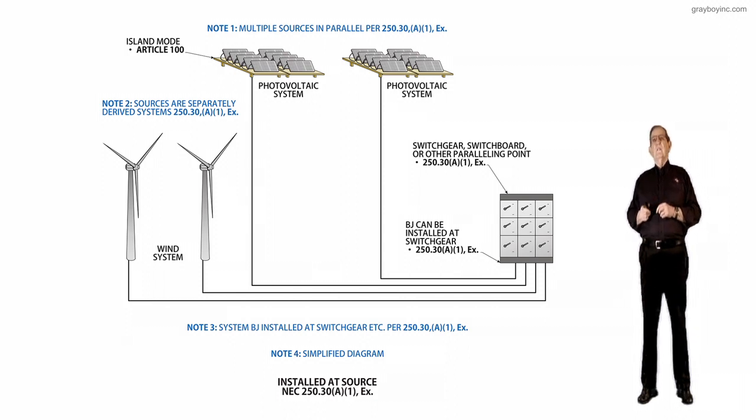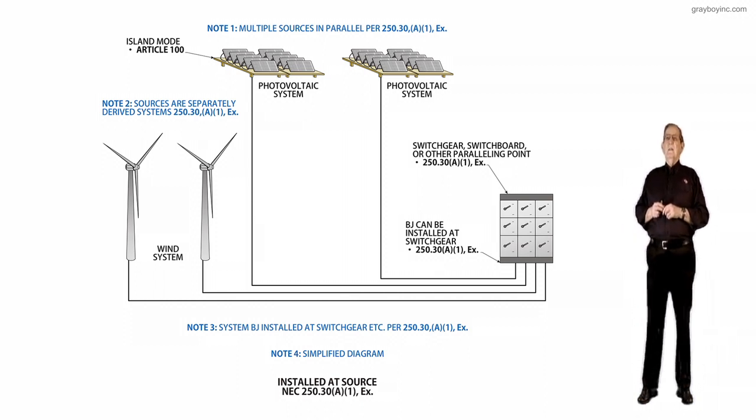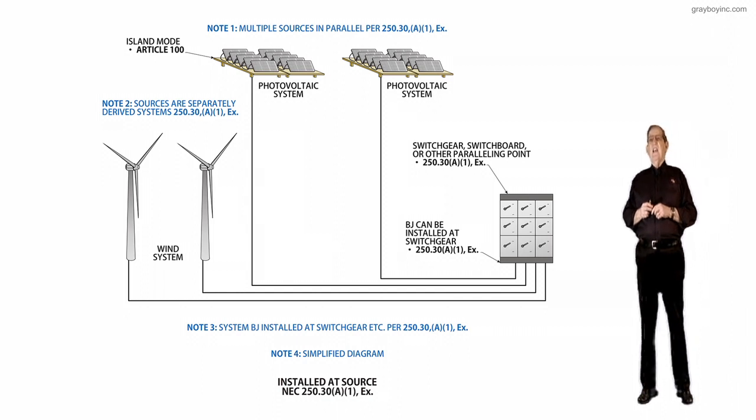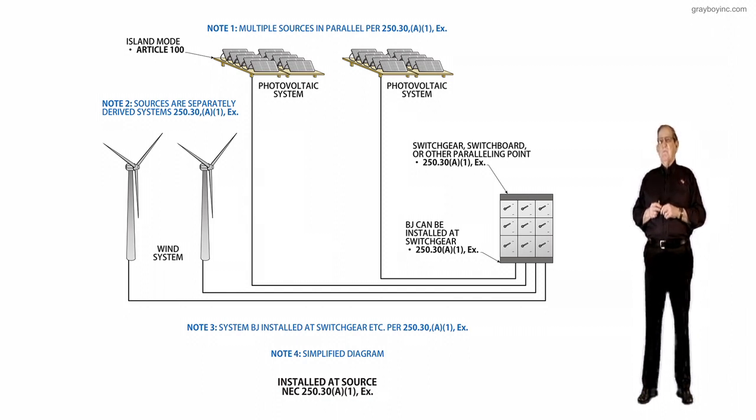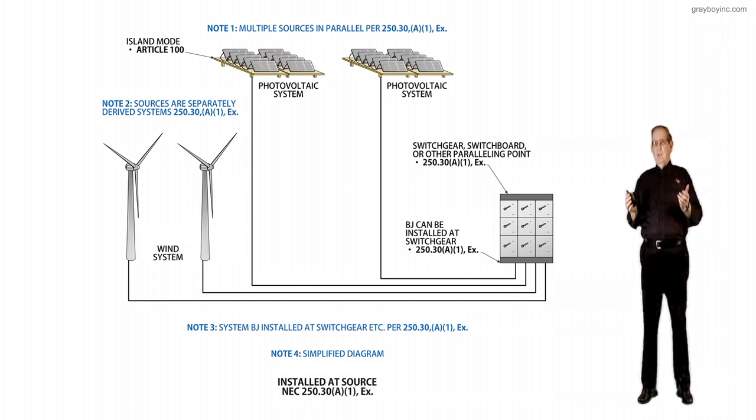And then notice at the service equipment, it's switchgear, panel board, or the paralleling point that takes place as permitted in 250.30A1 exception. And then notice that the bonding jumper can be installed at switchgear as permitted in 250.30A1 exception again.